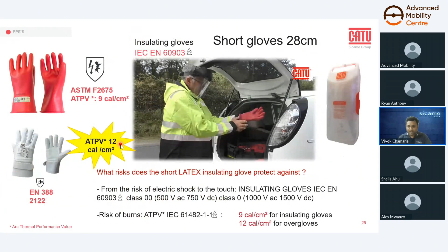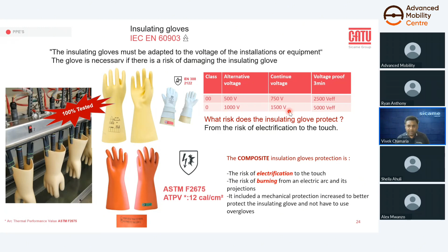Over-gloves are there again with arc protection, and the gloves ranges start from class 00. Class 00 means 500 volt on AC, 750 volt on DC. If you think your risk factor is more than 700 or 800 volts, it's better to go with class 0, which will comply with 1500 volt DC equipment. So the right selection of products is very much important.